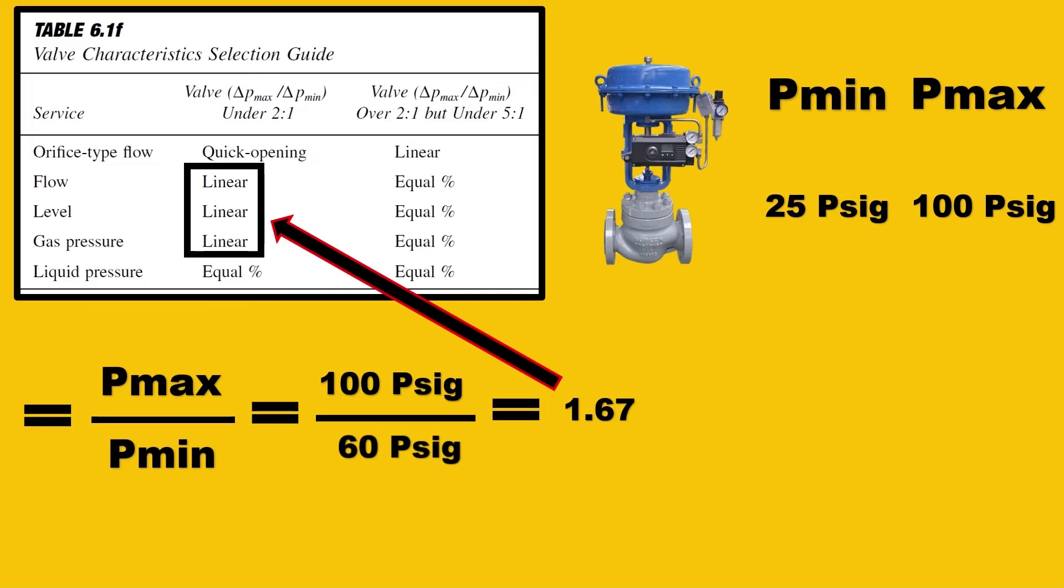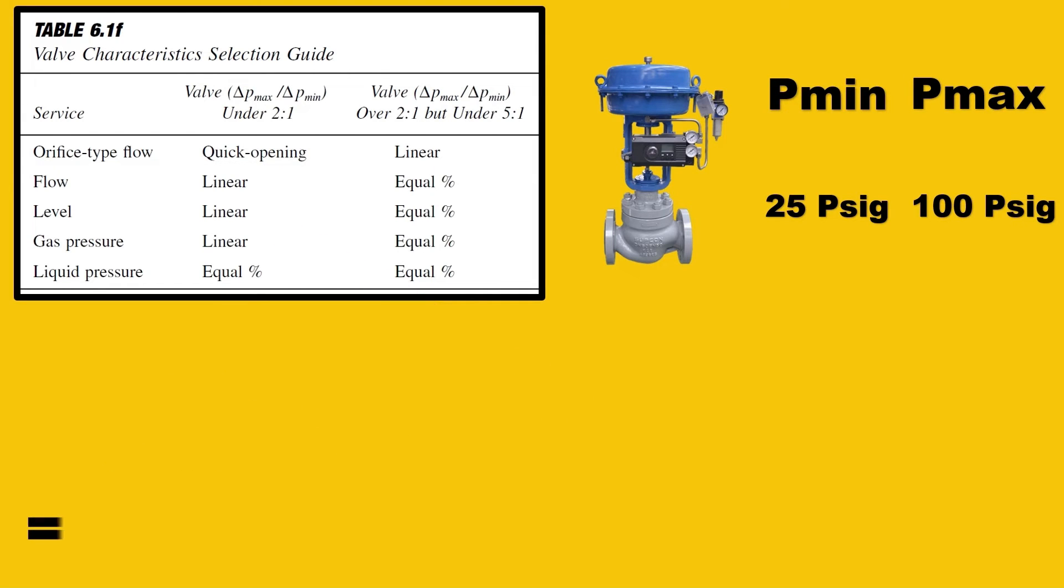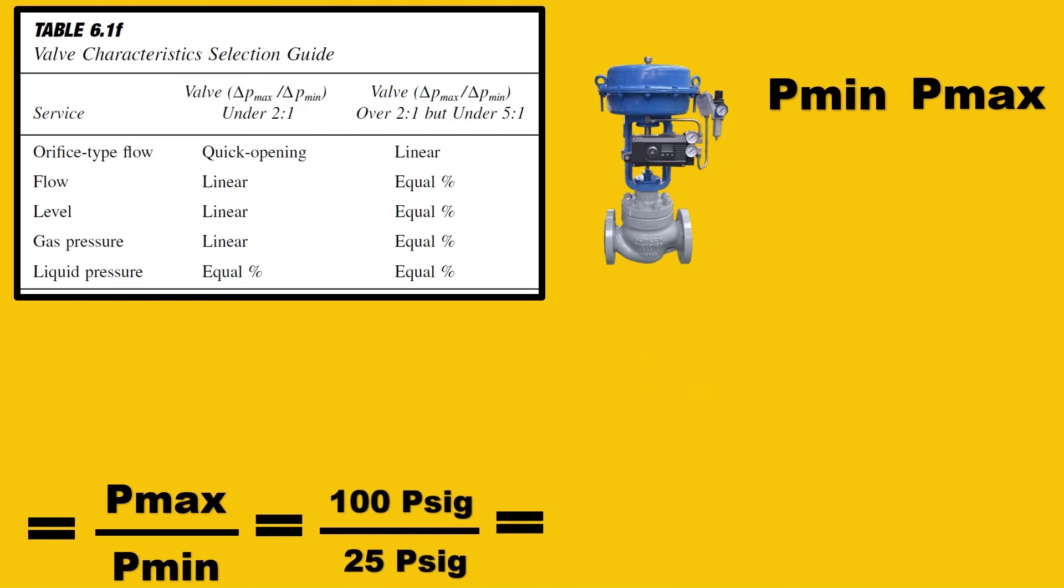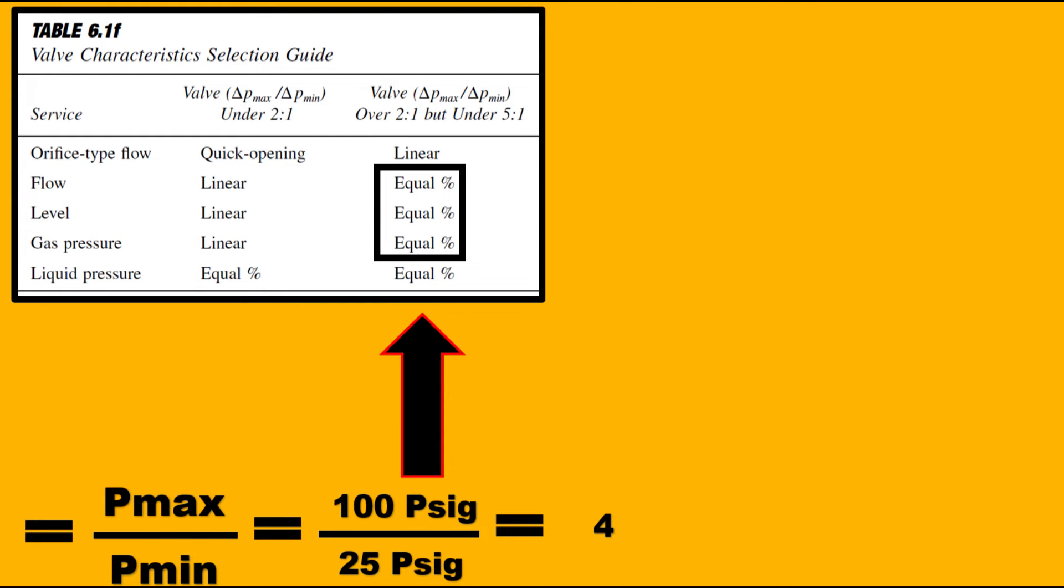If the pressure variation is more, for example 100 to 25 psig, when you calculate 100/25, you get 4, which is greater than 2. So you go for the second column, which recommends an equal percentage valve.